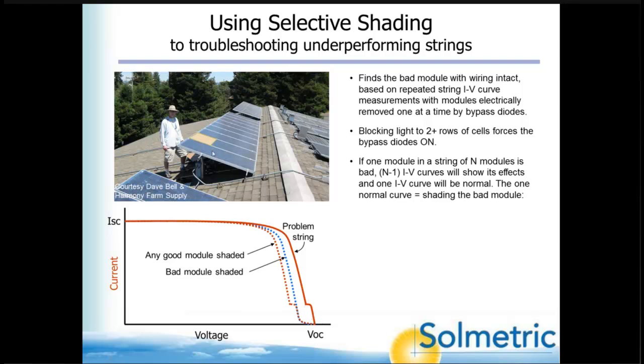So we measure this string of modules 10 times, which is quite quick, each time putting the cardboard over a different module in the string. And what we're going to see is 9 traces like the dotted red trace that have the step in it yet, and 1 trace like the dotted blue one that does not have the step. And that dotted blue one corresponds to when we shade the bad module. So that's the selective shading method, and we've been telling everybody under the sun about it because it's such a powerful method for troubleshooting down to the module level without so much time and without disconnecting and reconnecting and removing so much hardware. It can really be a nuisance, and it can introduce workmanship errors.